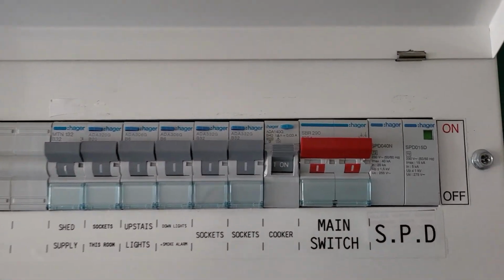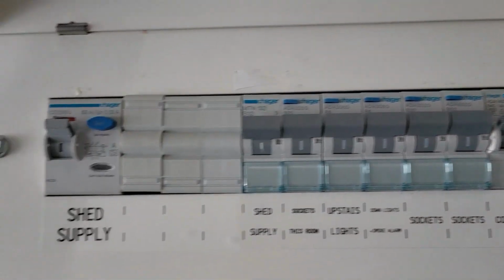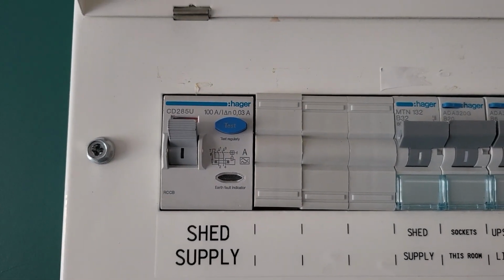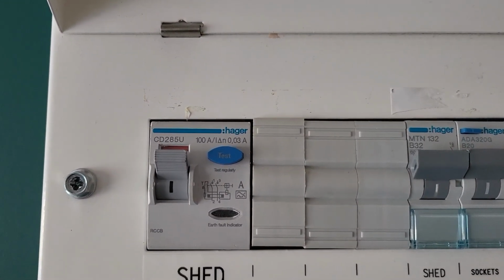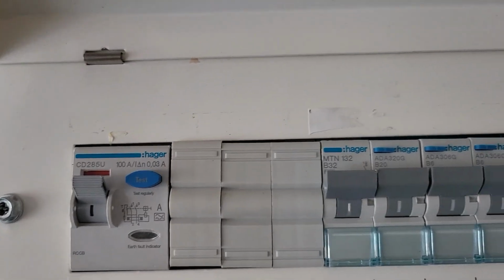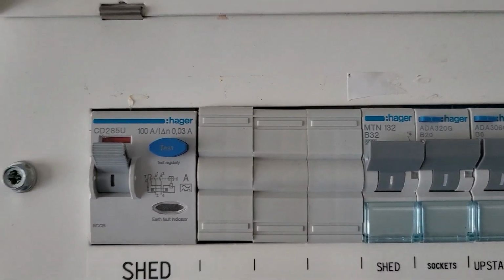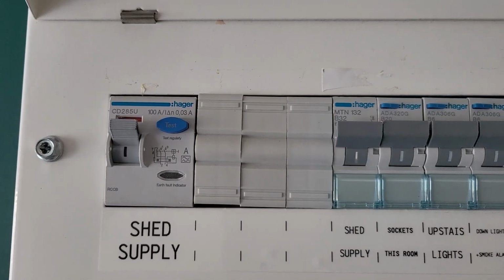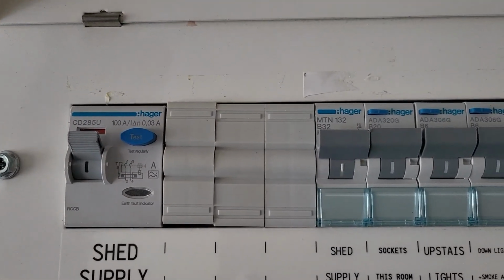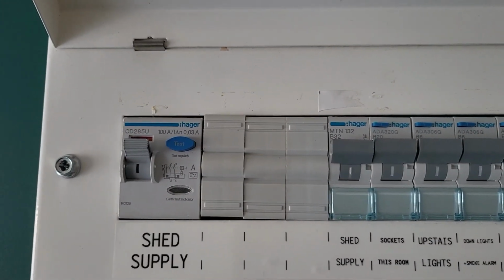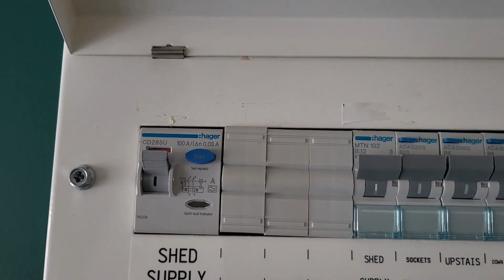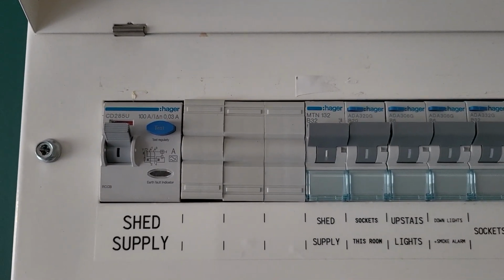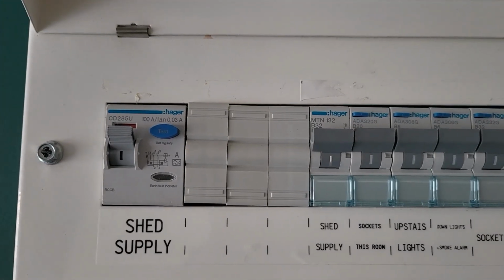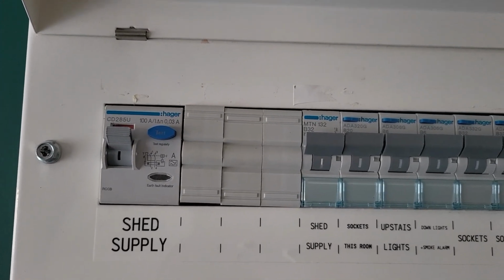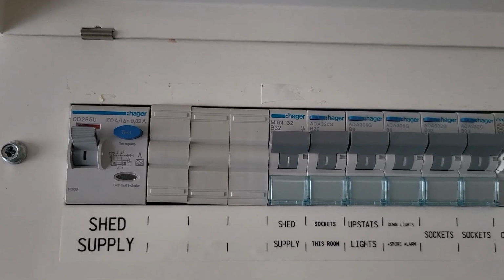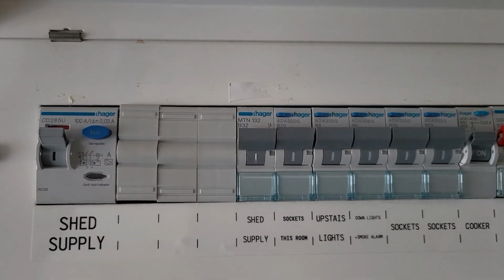So we can see in the board there we've got the main switch with the SPD, and down the end here we've got this double pole RCD which leads off out to the shed. We've also got an MCB there that looks after it as well. Not gone for the RCBO on the Hager because it is just single pole and a solid neutral, and we wanted the RCD to open both poles because we are down on an earth electrode at the shed. So just made more sense for us to set it up like this. Obviously this isn't how you would perhaps tackle it on your installs, but works a treat here.